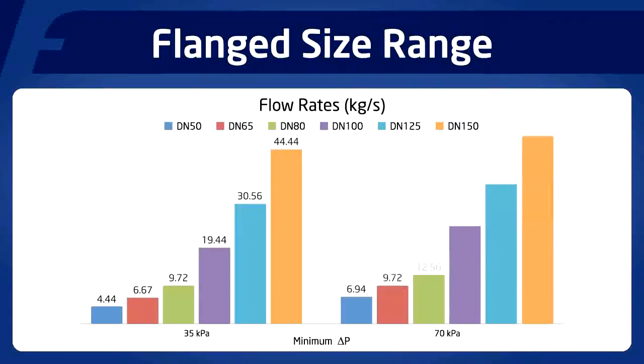We have both a low pressure and a high pressure version of the valve. The low pressure has a minimum startup of 35 kPa and a maximum pressure rating of 600 kPa. And as can be seen on the slide, from flow settings from 4.4 litres per second maximum on a DN50 to around 44 litres per second on a DN150.